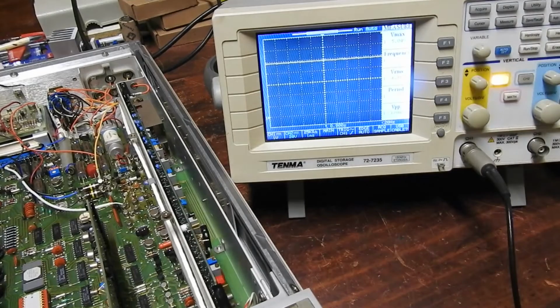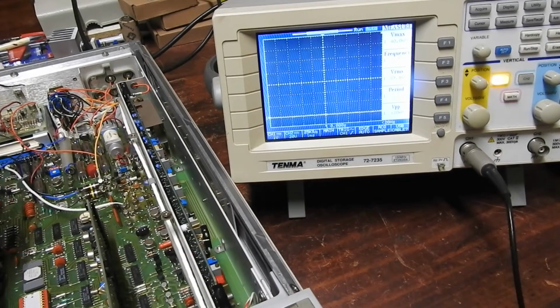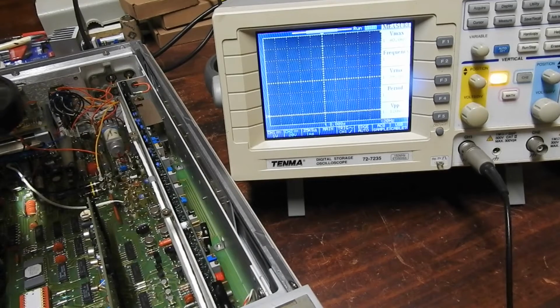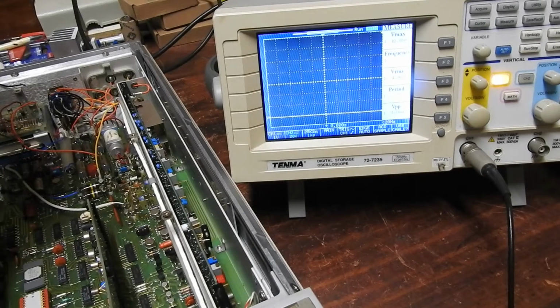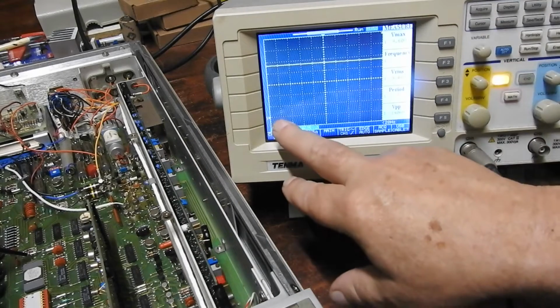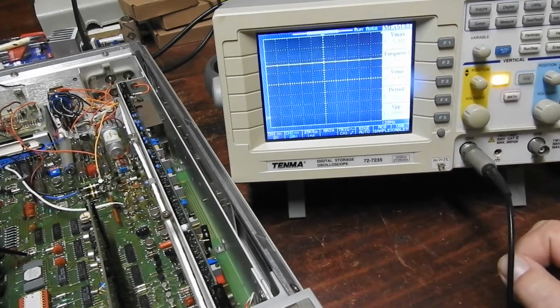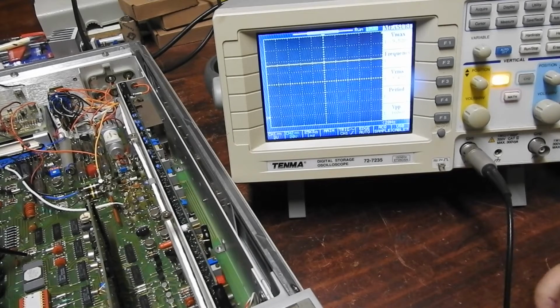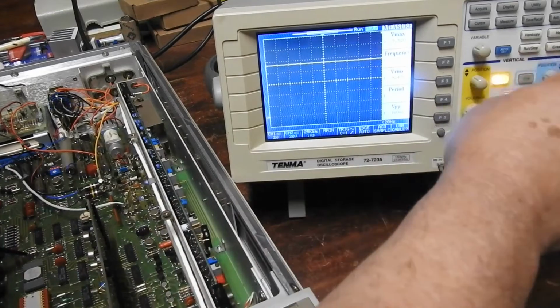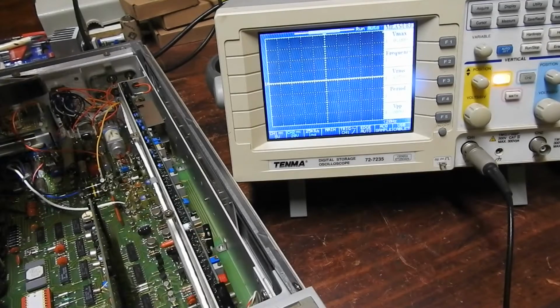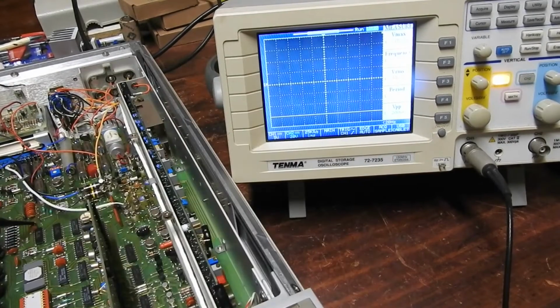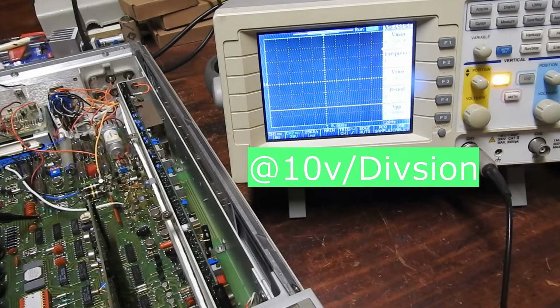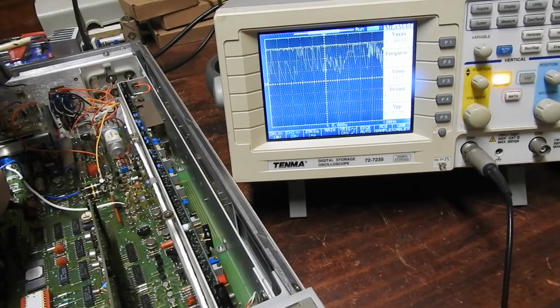Now we'll check the in-guard voltages, and the in-guard frame is ground, plus 5 on the in-guard, also looks pretty good, plus 9, going down to 2 volts per division, plus 9 is 9.5, 9.6, probably good, looks pretty straight. Next, put this up in the centre, 5 volts per division, minus 15, that looks pretty good, minus 15.2, plus 15, also good, minus 24, good, and plus 30, also good. Yeah, so all the supplies are good in this.